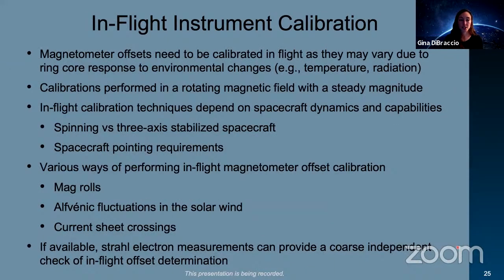But then in-flight calibration is also necessary for the offsets. So we're not calibrating the orthogonality or the scale factors in flight, but we are still calibrating the offsets. They need to be calibrated because they might vary in flight due to the ring core's response to the environment. The permalloy material that I talked to you about, the heart of the ring core, might, due to different environmental changes, affect how the offsets of the measurements are being measured. That has to do with maybe changes in temperature or radiation of the environment, and it's something that we're able to calibrate in flight. We do this by performing the calibrations in a rotating magnetic field that has a steady magnitude. There are several ways to do this, and I'll talk to you about that in a second.